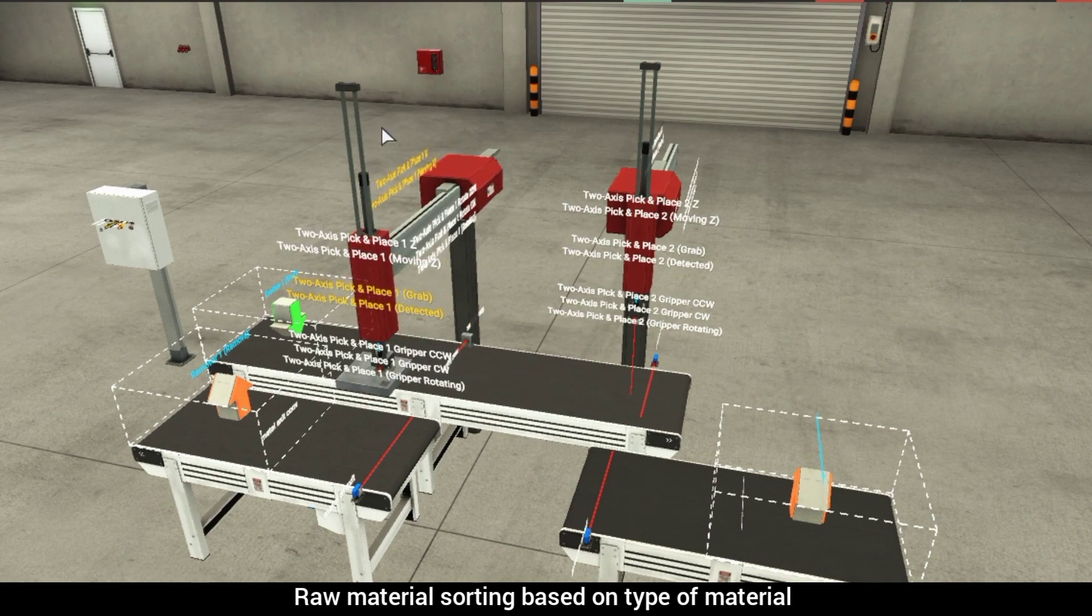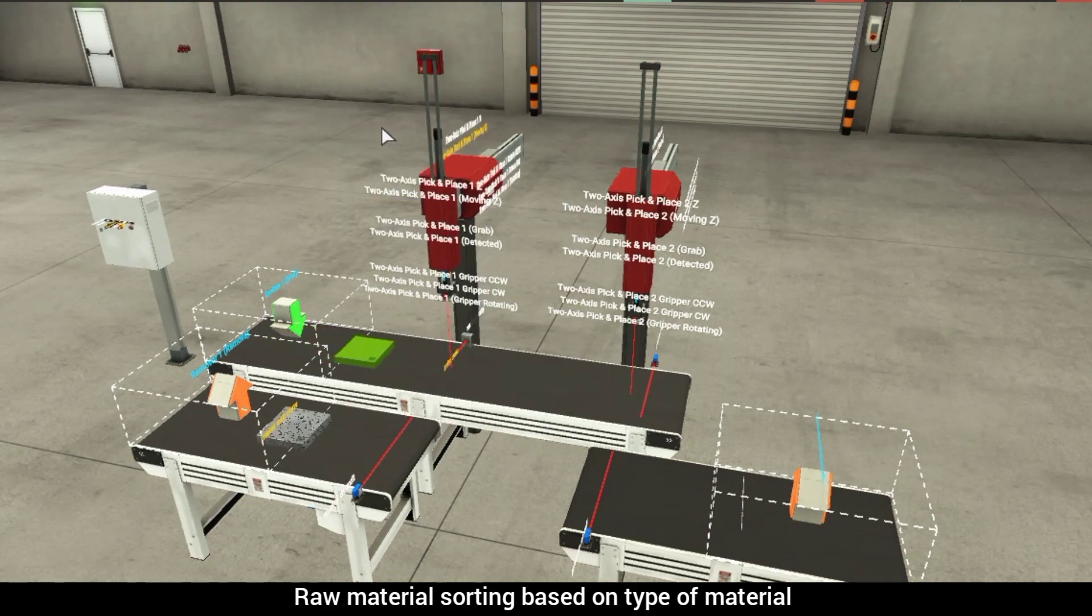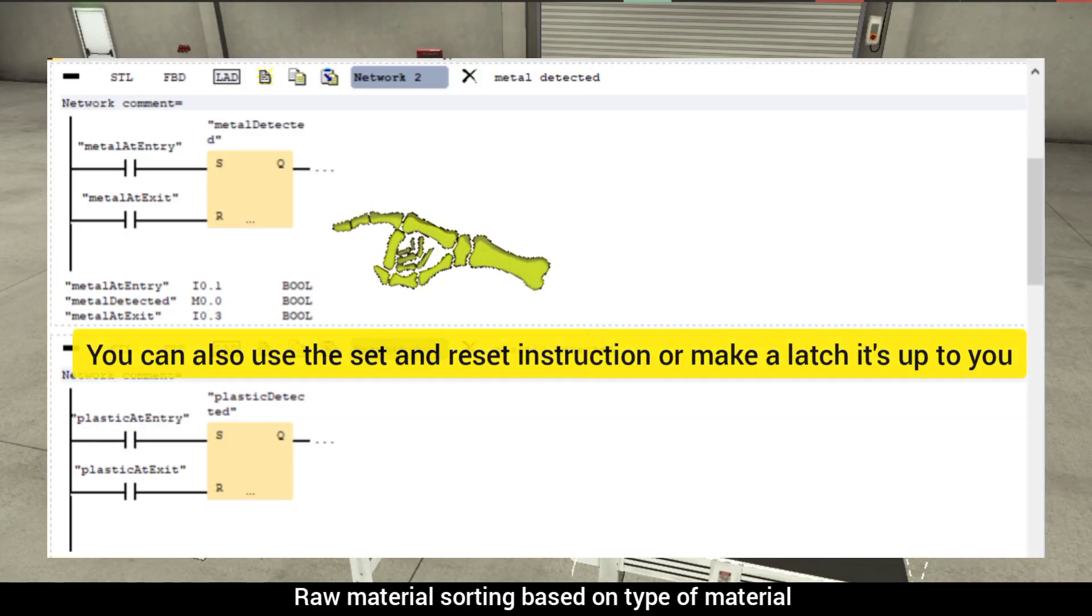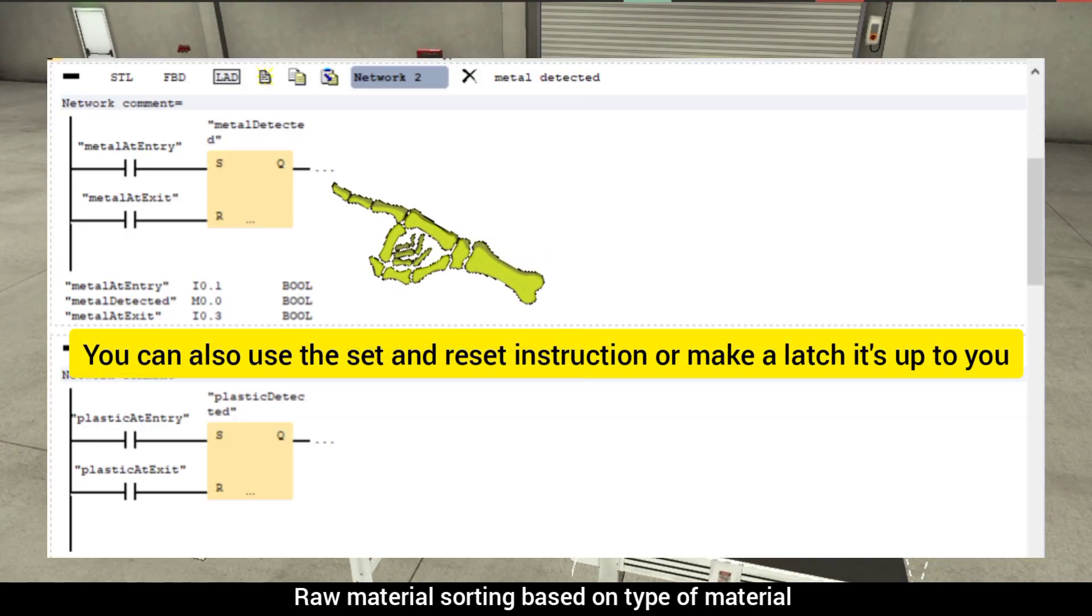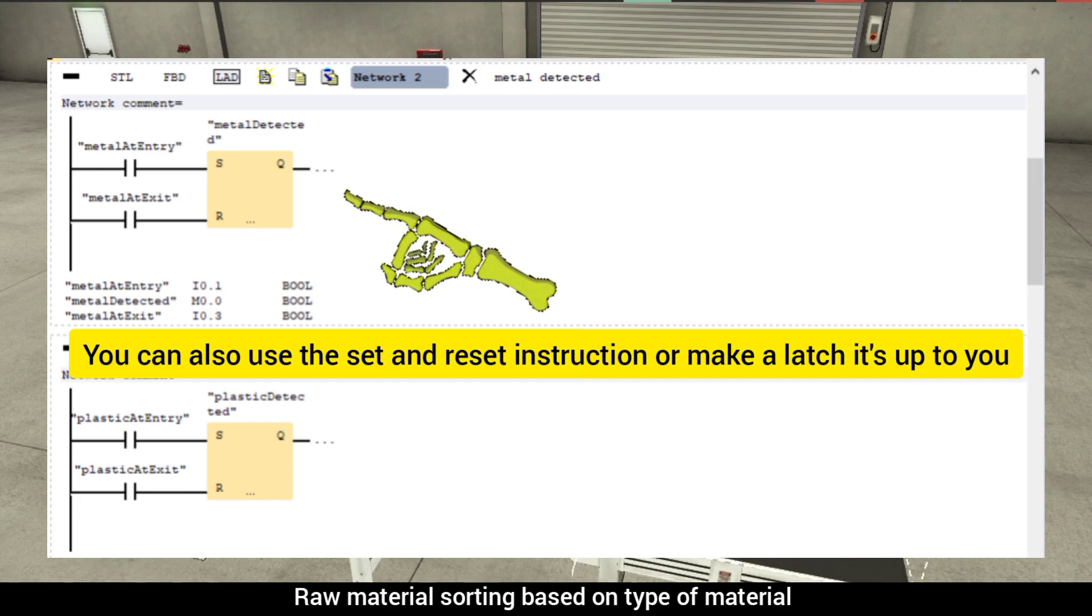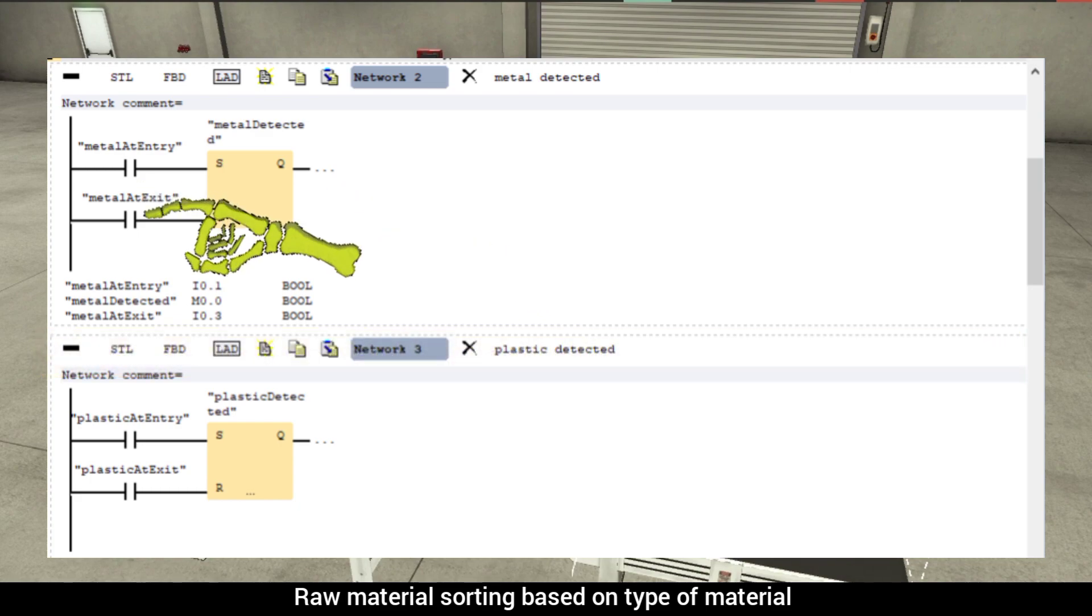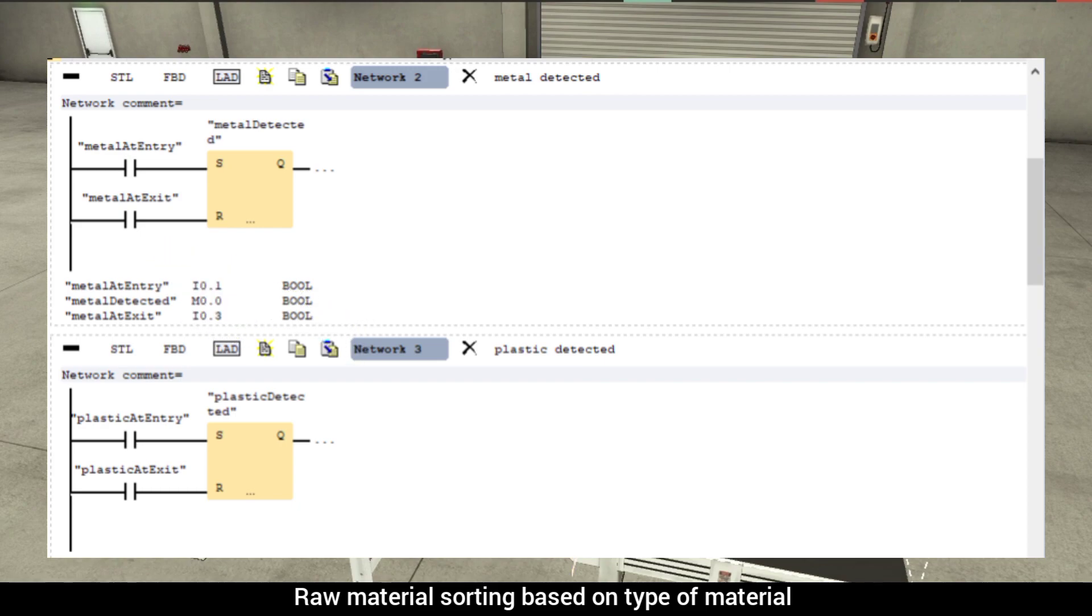To set these memory bits, we can make use of a set reset flip-flop and connect the set input to the sensor on the entry conveyor and reset input to the sensor on the exit conveyor.